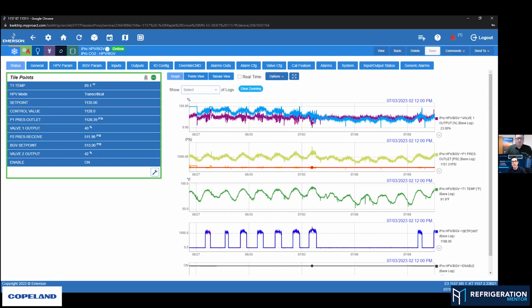Yeah, and one of the big things is that you want to trend it, you want to look at it, but you don't want to change anything. I've seen this time and time again. A technician calls me up. If that system was commissioned properly and it's been running for 6 months or a year, and somebody went back and just fine-tuned it, a year comes by and then something craps out or something drastically happens and you're getting called out, you don't need to be going in and changing parameters. It's usually something mechanical or something failed, like a pressure transducer, temperature probe, a valve may have failed, but you don't have to go in and start reprogramming the controller. If it's been running for a year, fine. Changing set points is usually not going to fix your problem.